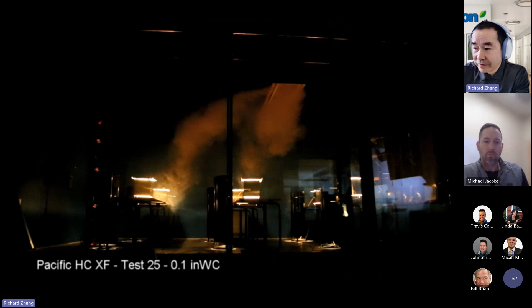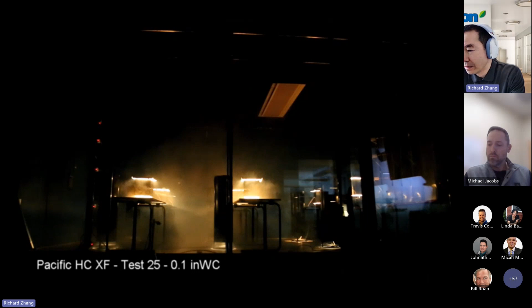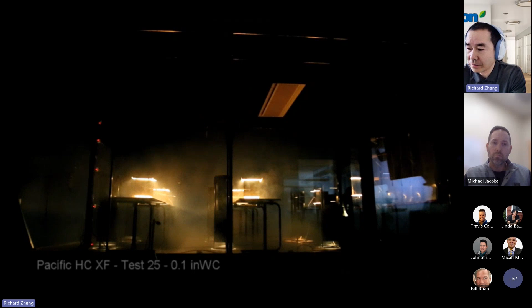However, if you have a VAV chill beam just in front of the constant airflow beam, when you barely close the damper a little bit, this is what happens because they lost the velocity. The first thing you see is they dump the air onto the person right below the chill beam. Also, make sure you watch to the end of this video clip. The air never ever goes back to the chill beam. In other words, they lost capacity.